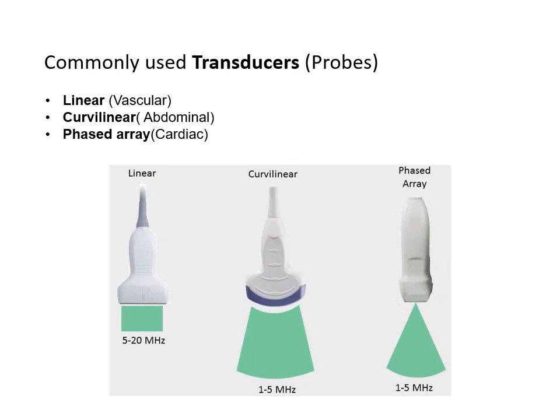There are three commonly used probes in acute settings. The first is the linear probe, which has a flat face and the highest frequency. The second is the curvilinear probe, which has a curved face. The third is the phased array probe. The curvilinear and phased array probes have slightly lower frequency compared to the linear probe. Lower frequency probes are used for deeper structures such as abdomen, aorta, or heart, while the linear probe with high frequency is used for superficial structures such as nerves, tendons, IV access, and foreign bodies.